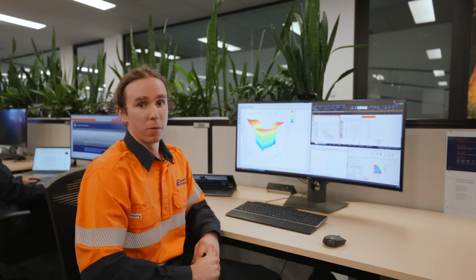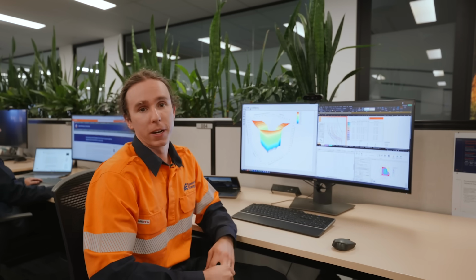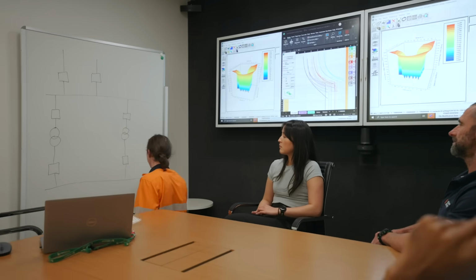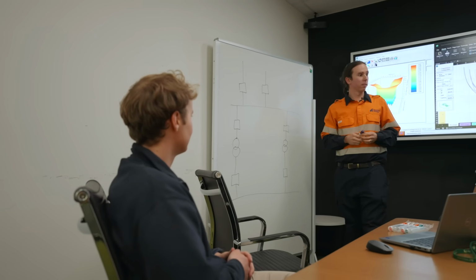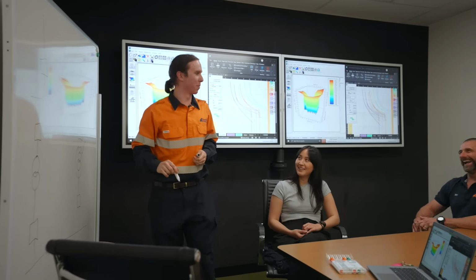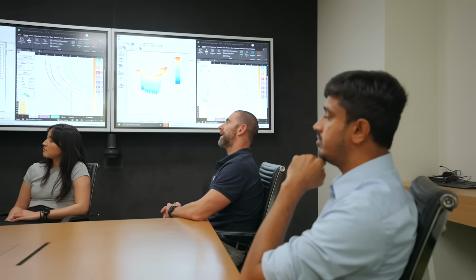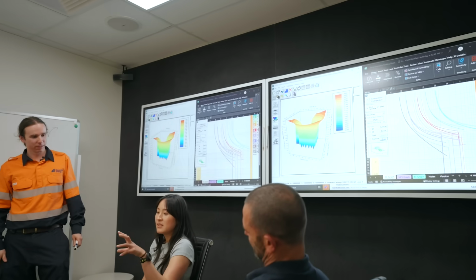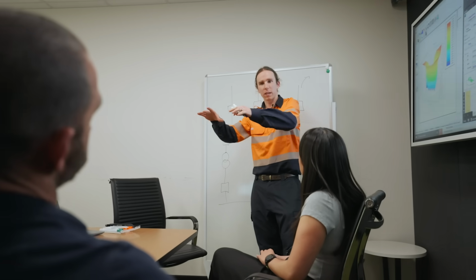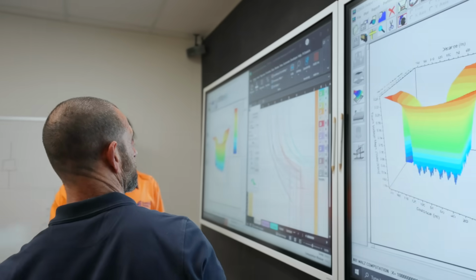From here, I'll want to work with other stakeholders across the business - talking with our planning and zone substation engineering teams to investigate if there are any transformer upgrades at this site or further upstream which might affect the available fault level. I'll also investigate possibly changing some of the fault clearing times by adjusting the protection settings, and talk with our zone substation design team about any changes to the physical layout of the site. From there, we'll assess the performance against all relevant safety criteria from industry guidelines and Australian standards.